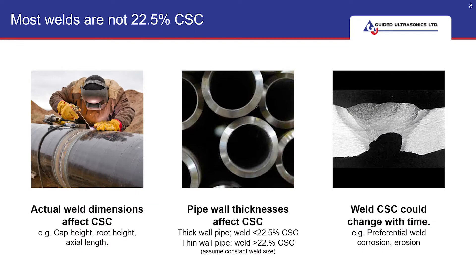However, in most cases, this assumption may not be as accurate as you think. This is because the cross-sectional area change is affected by the actual weld dimensions, which can vary from weld to weld, especially in field welds. Secondly, pipe wall thicknesses also affect the cross-sectional area change of welds — a weld with fixed dimensions will give a smaller cross-sectional area change when found in a thicker wall pipe. Thirdly, the weld cross-sectional area change could change with time due to weld corrosion and erosion effects.